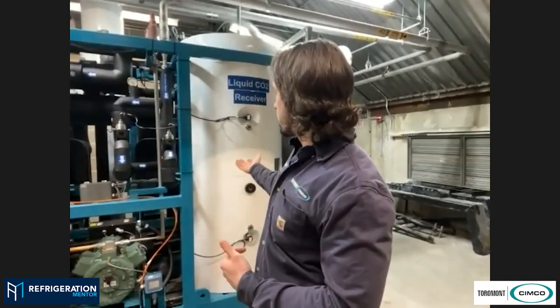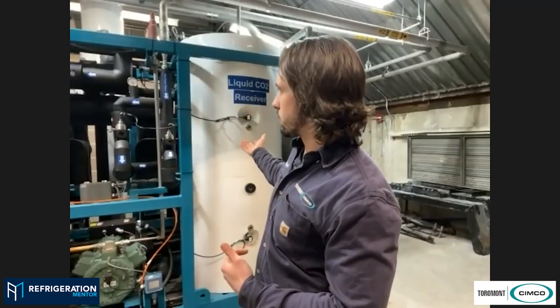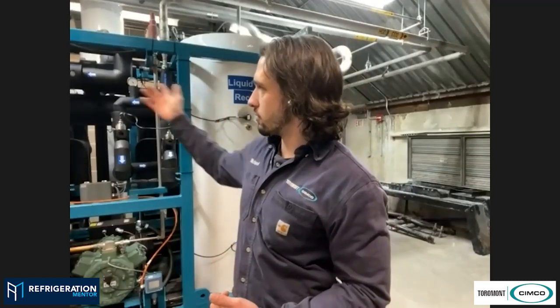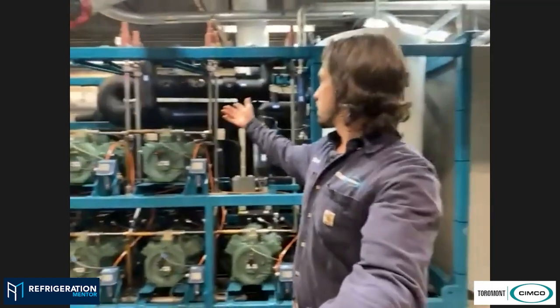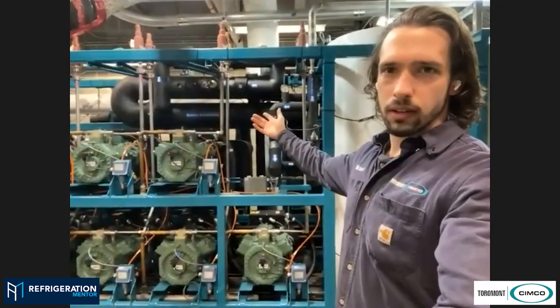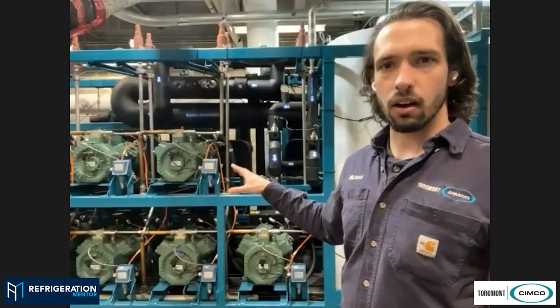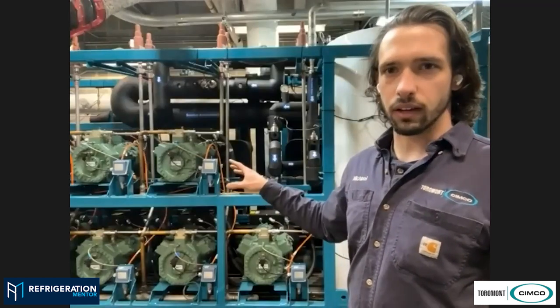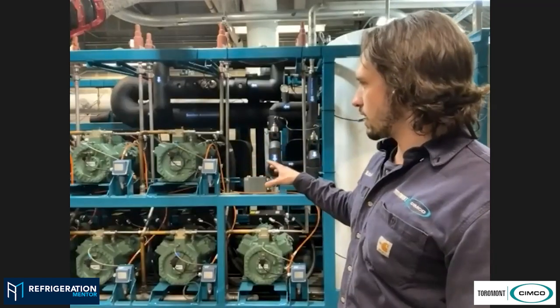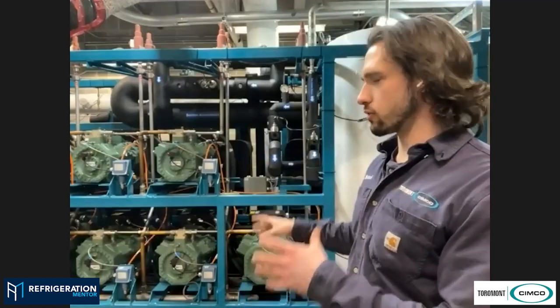Any flash gas that we need to recycle is recycled into the common suction group through our recycle valves. There's no dedicated machine on the system for recycling flash gas. And like I said, it's not a two-stage system, so there's not a low and a medium temp suction group. There's only one common suction group for these machines.